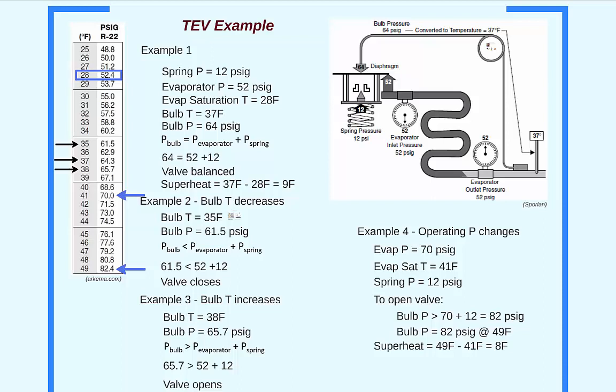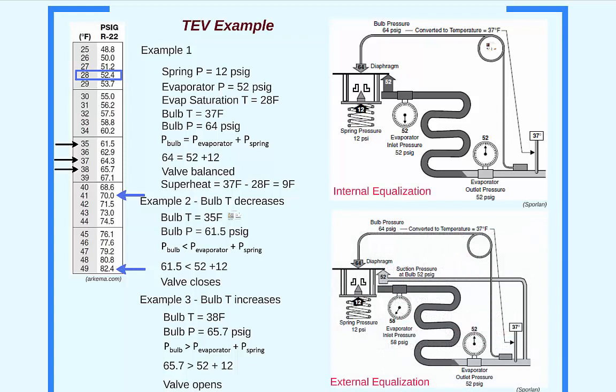This is an entirely mechanical control, which still requires calibration, but is not dependent on electricity or control signals. The evaporator's operating pressure may be connected to the thermostatic expansion valve at the evaporator inlet, known as internal equalization, or the evaporator's outlet, known as external equalization. Internal equalization is sufficient for smaller systems. However, larger evaporators will have higher internal pressure drops between the evaporator inlet and outlet.